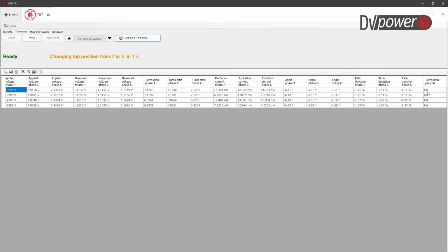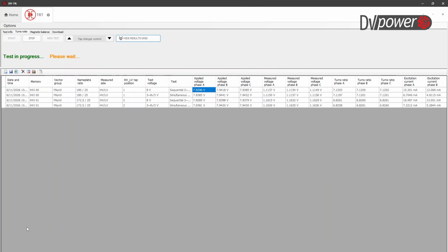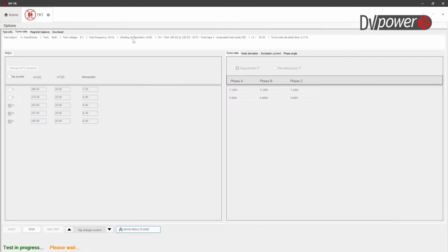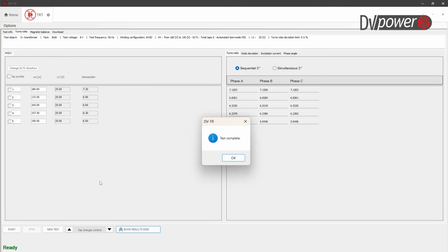So for every phase up to now, this transformer failed. Turns ratio is not according to standard. We will hide results grid. Once measurements are done, our software will notify us. Test is completed. We press OK.